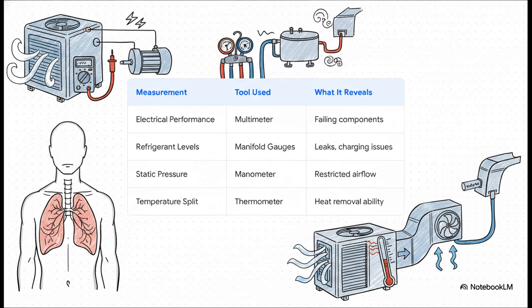And this is how they get their answers, with hard data, not just guesswork. They'll use a multimeter to check the electrical vital signs of motors and other components. They'll hook up digital gauges to measure refrigerant pressures, which can point to leaks or other issues. They'll use a manometer to check static pressure.